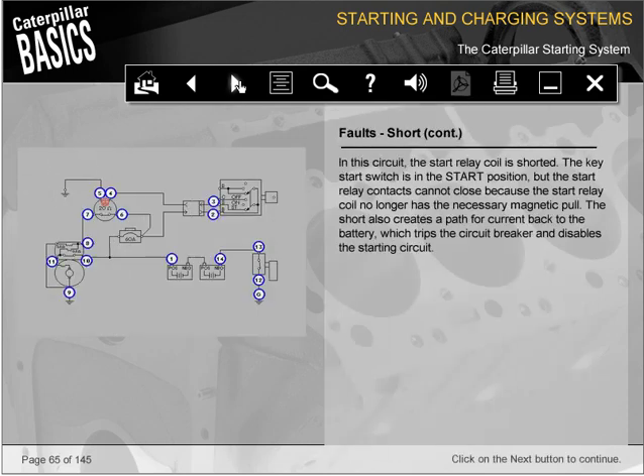In this circuit, the start relay coil is shorted. The key start switch is in the start position, but the start relay contacts cannot close because the start relay coil no longer has the necessary magnetic pull. The short also creates a path for current back to the battery, which trips the circuit breaker and disables the starting circuit.